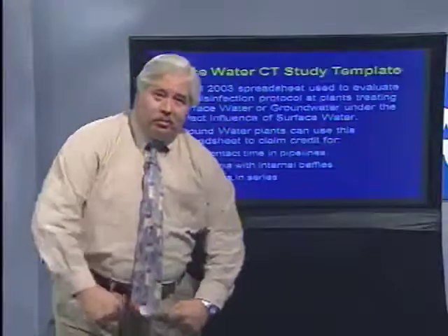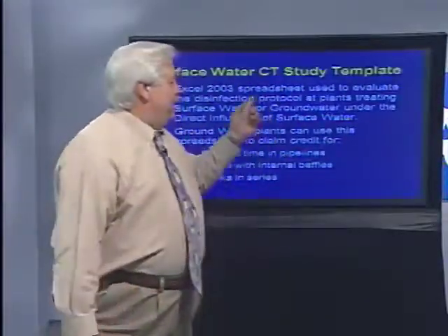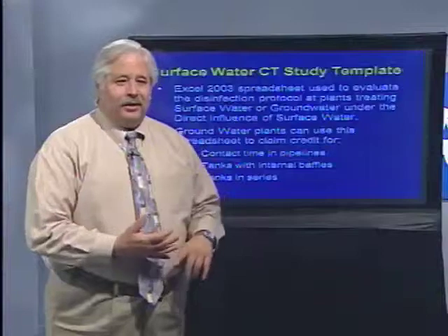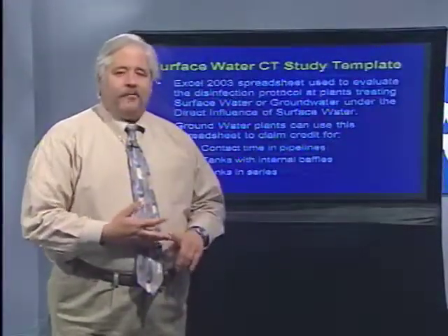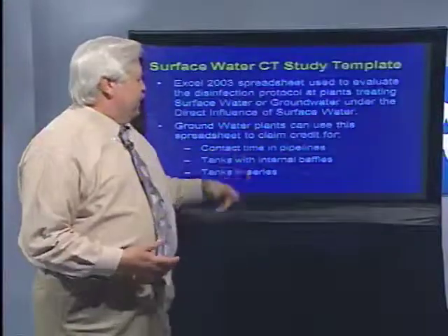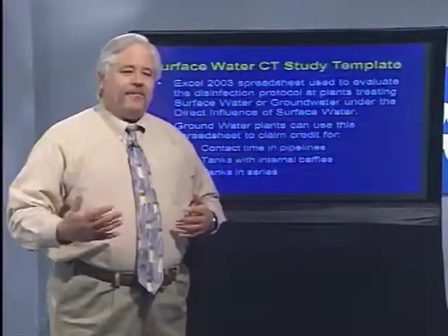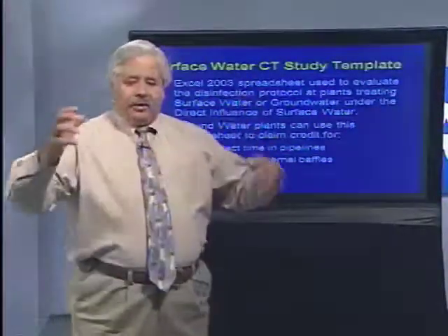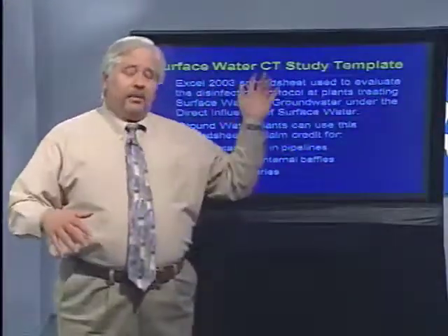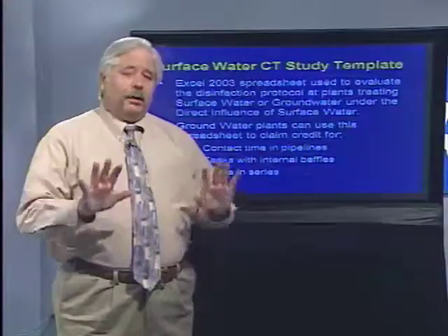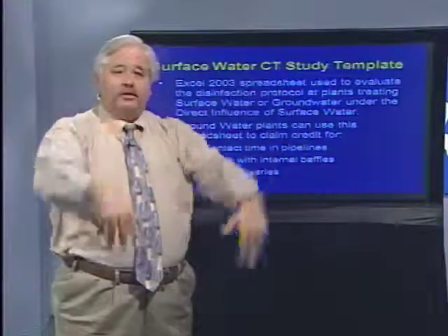It's a much more powerful tool. It deals with other disinfectants like chlorine dioxide and ozone. It allows you to claim credit for pipelines. It allows you to claim credit for tanks that have internal baffles. It allows you to claim credit for tanks that are in series, because the groundwater CT study spreadsheet only applies if the tanks all fill and drain together.